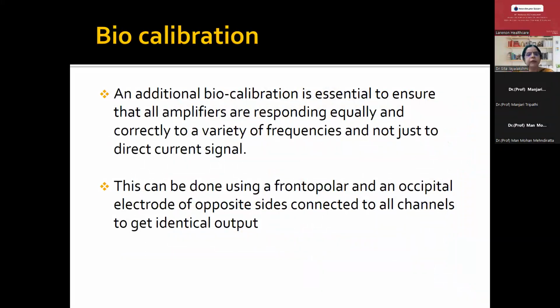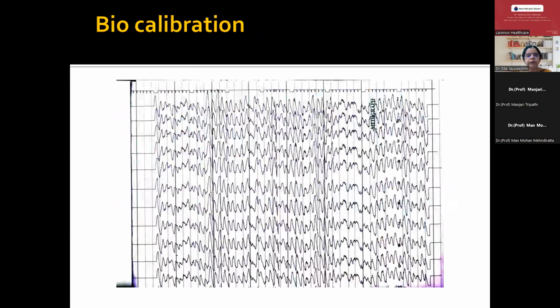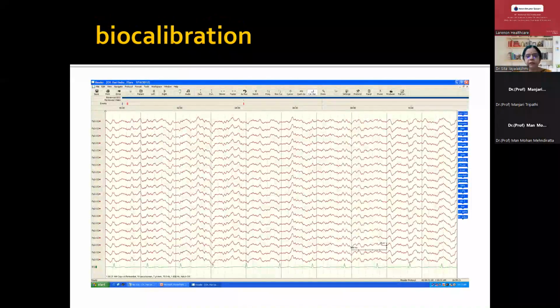The next step is the biocalibration. In addition to mechanical calibration, biocalibration is also essential to ensure that all the amplifiers respond equally and correctly to a variety of frequencies and not just to direct current signal. So the frequencies will vary across the entire brain. This is usually done by using a frontopolar and an occipital electrode of the opposite side, both connected to all the channels to get an identical input. This is the biocalibration of an analog machine, and this is the biocalibration of a digital machine.